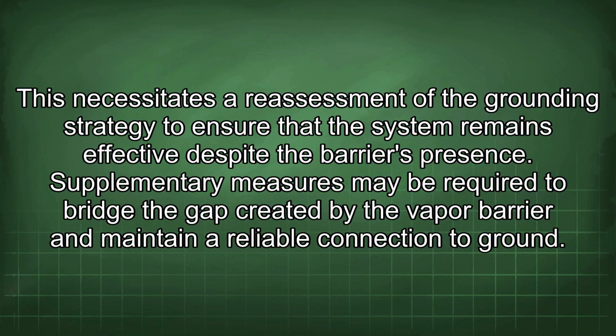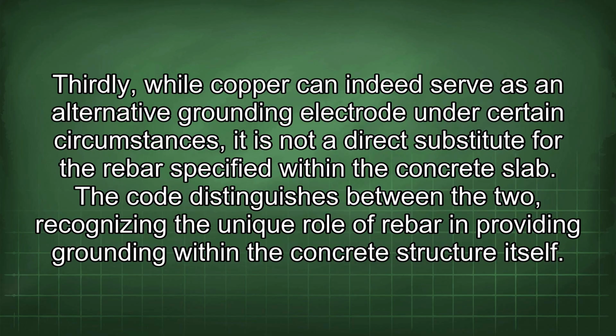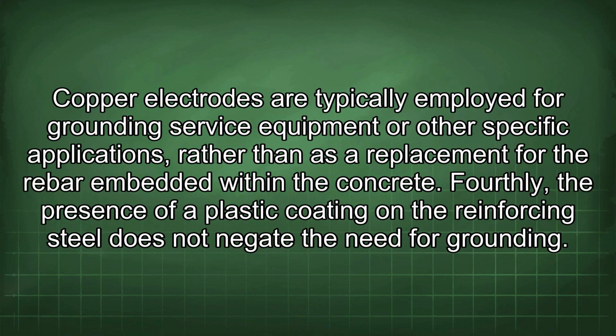Thirdly, while copper can indeed serve as an alternative grounding electrode under certain circumstances, it is not a direct substitute for the rebar specified within the concrete slab. The code distinguishes between the two, recognizing the unique role of rebar in providing grounding within the concrete structure itself. Copper electrodes are typically employed for grounding service equipment or other specific applications, rather than as a replacement for the rebar embedded within the concrete.